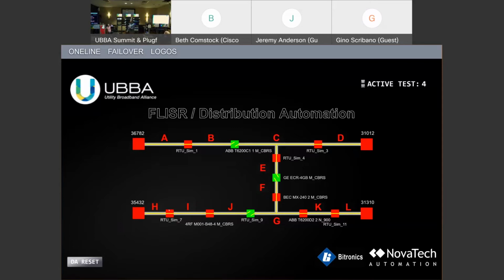So there's fuse saving, fuse blowing mode, coordination, communication, but we need to confirm the state of all of those devices. So the master station goes out and polls everybody and says, what is your current operational state? Sometimes they ask you, what was your current load state? Because we have that normally open, and we're going to close and refeed some of the grid from that normally open place. We want to make sure we don't overload another feeder. This could be two really long feeders. And if we have too much load in that area, we wouldn't necessarily want to close into it. Maybe we want to only re-energize 2 of 3 buses because we have more load than we can serve right now.